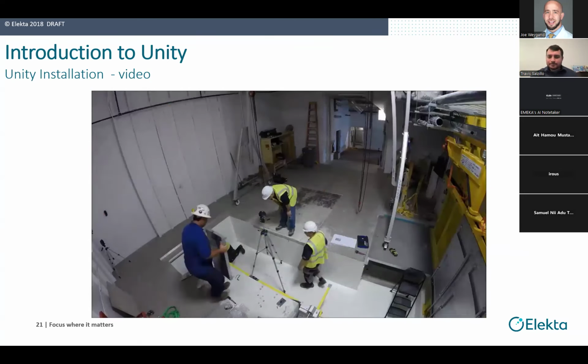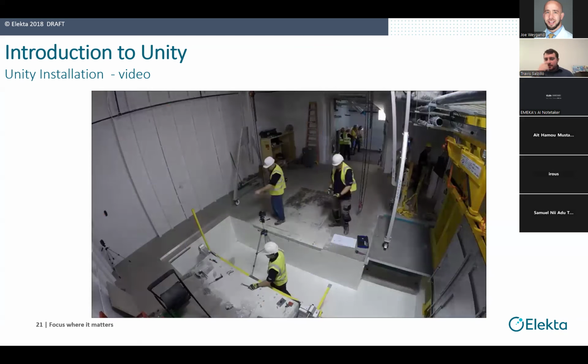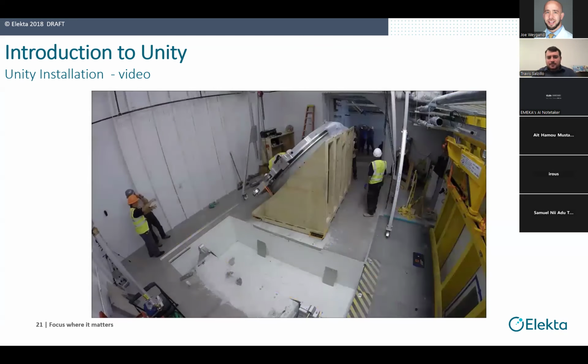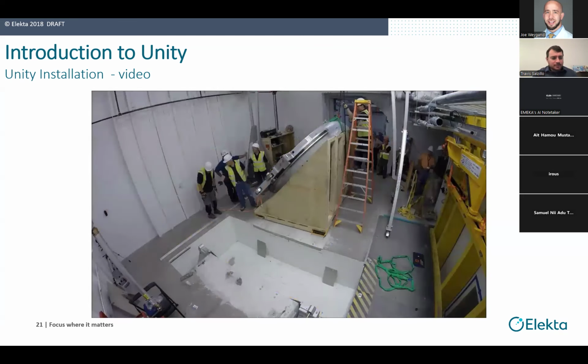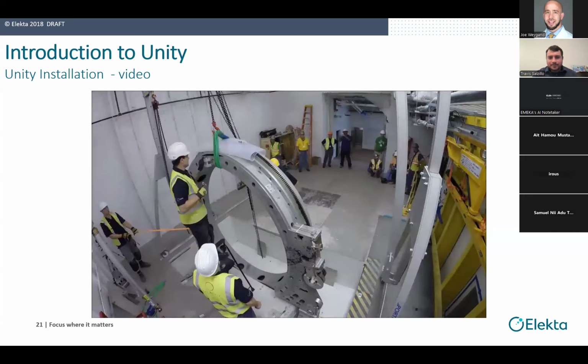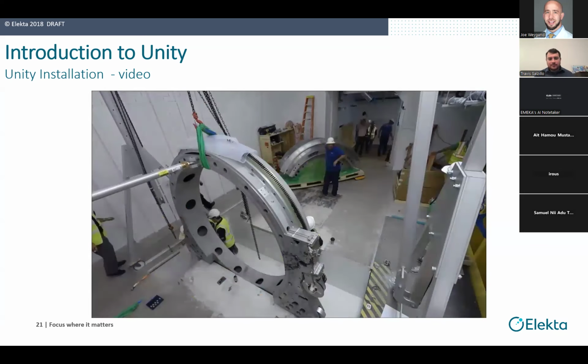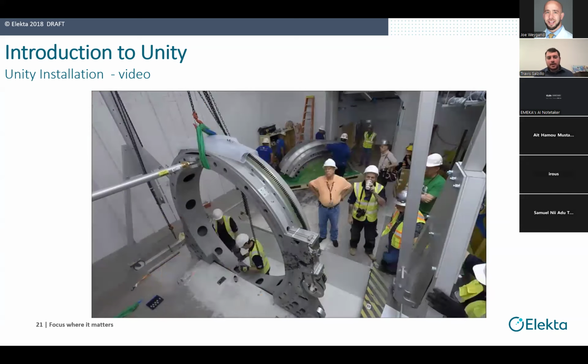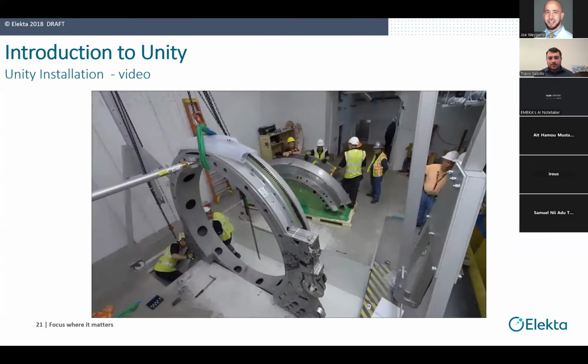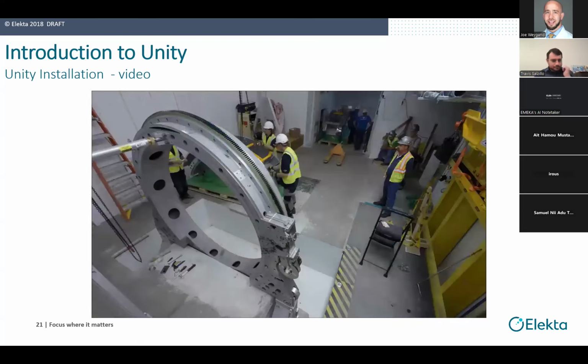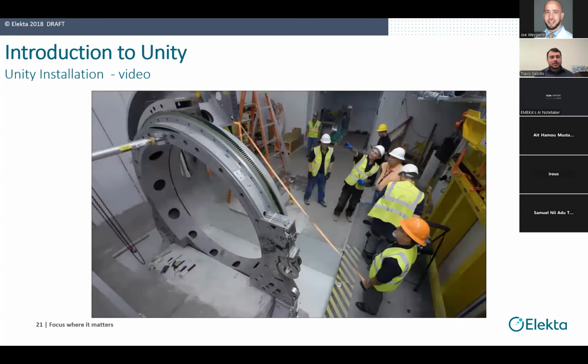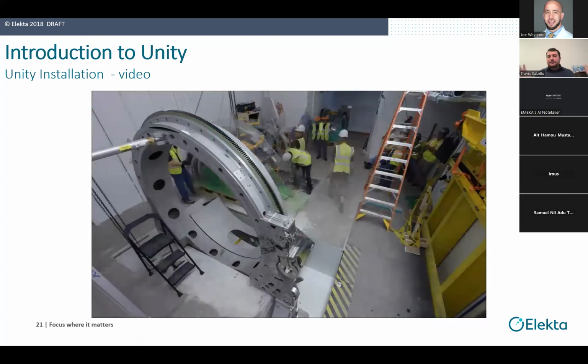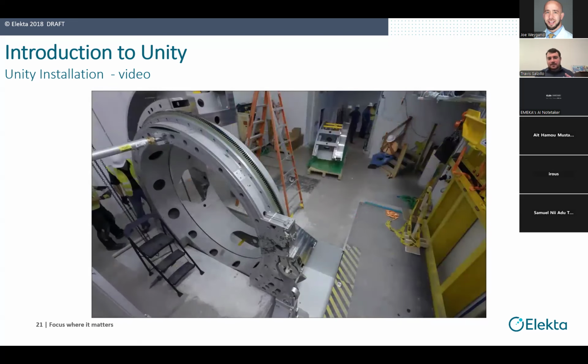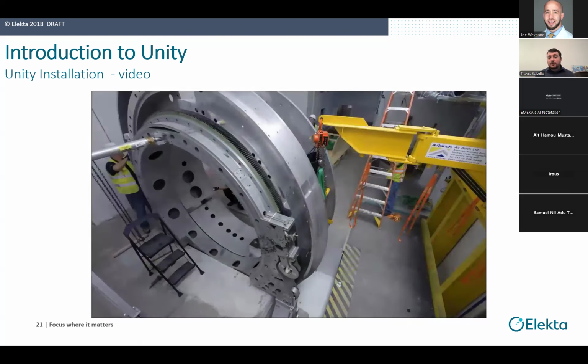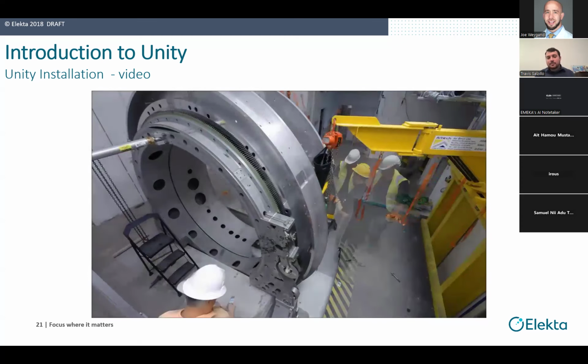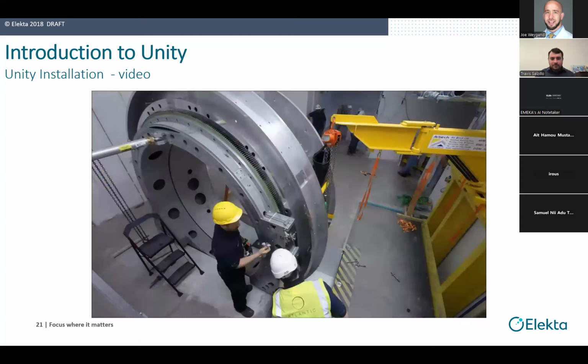So this is a vault that we dedicated to it. An interesting thing you'll see here is that because we have an MRI, it's not sufficient just to have your typical concrete vault. You have to have that for the high energy radiation. But then you also have to build an RF cage within the vault itself that basically keeps RF interference out, so your image quality isn't compromised. So you'll see here first, they're in the vault.